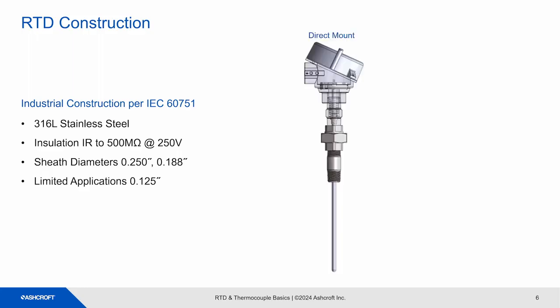There are direct mount style probes. The RTD sensor is at the tip of the probe. They use mineral insulated cables or MI cables. They have a customer-specified type of lag. The most common lag is the shown nipple-union-nipple lag. They have an electrical junction box or head directly mounted on the probe.